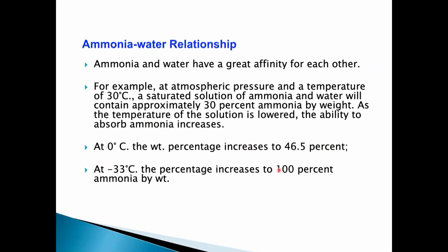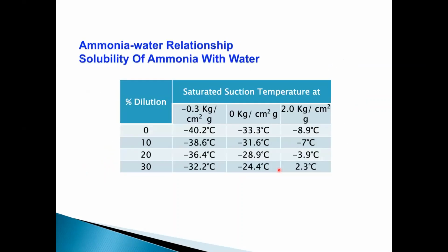So what does this mean? All the refrigeration charts are based on the purity of ammonia. It means 99.95% pure ammonia. Now, if you have impure ammonia, or ammonia with water, say 10%, which theoretically operating at minus 0.3 bar pressure would give you minus 40, you will operate only at minus 38.6. So it means you are almost losing 2 degrees centigrade.